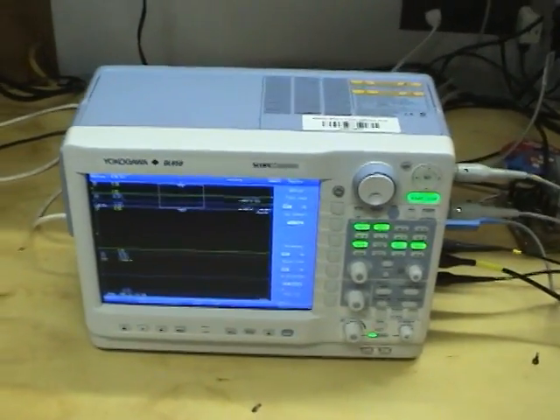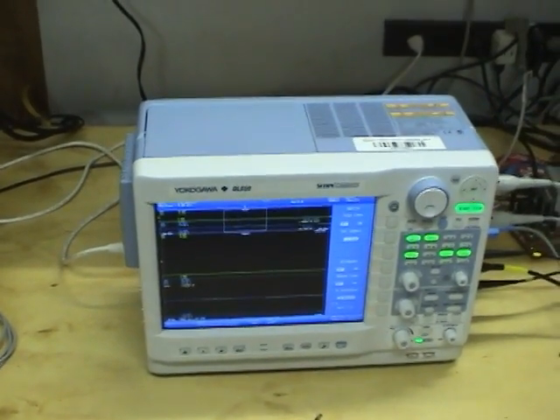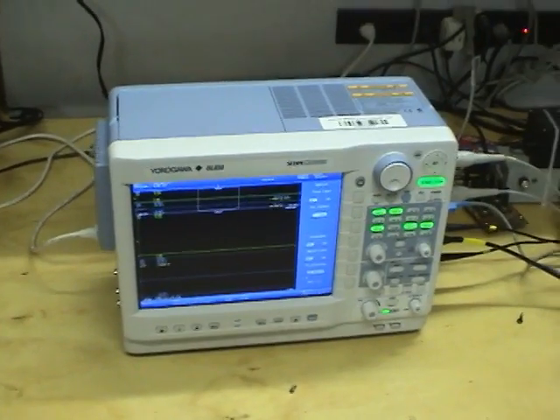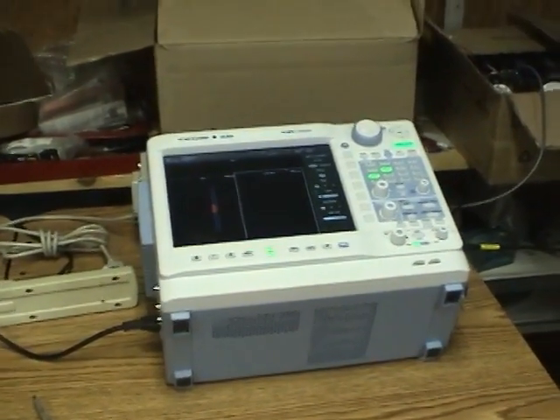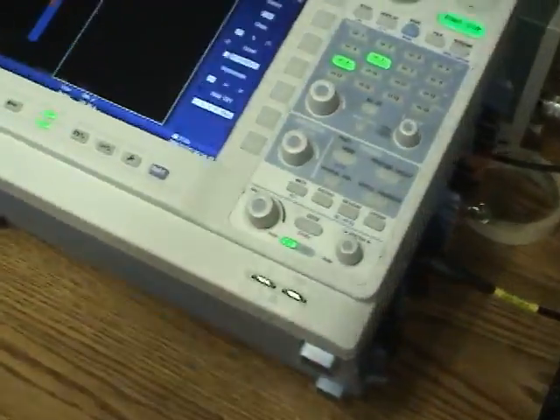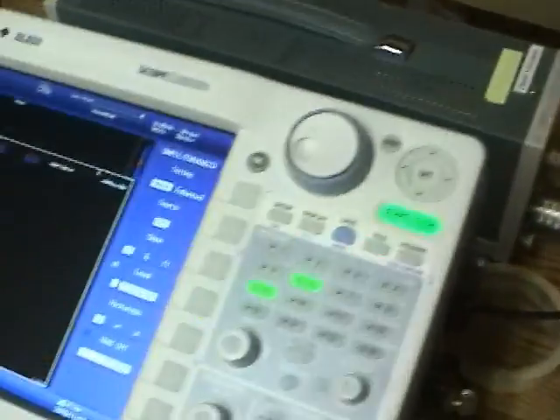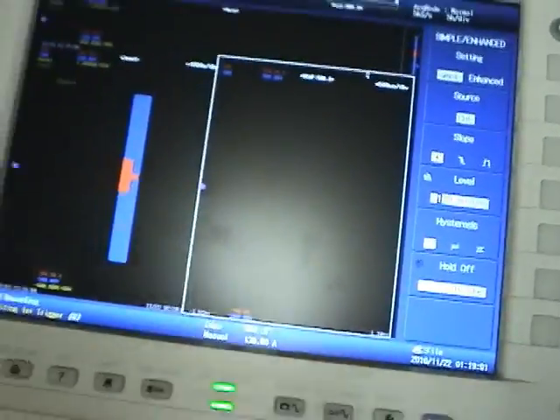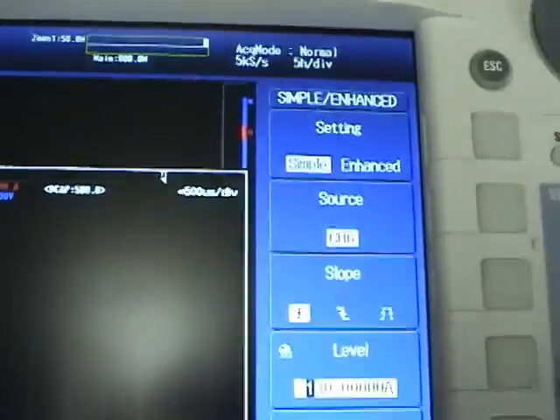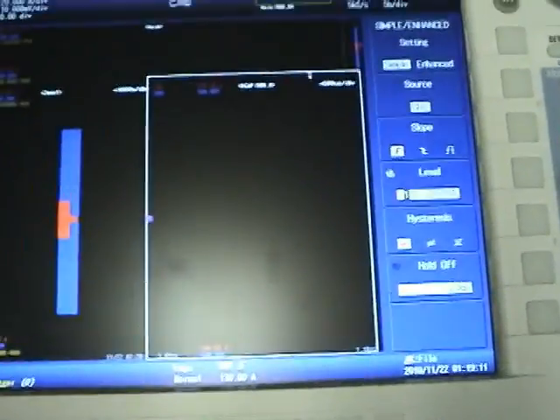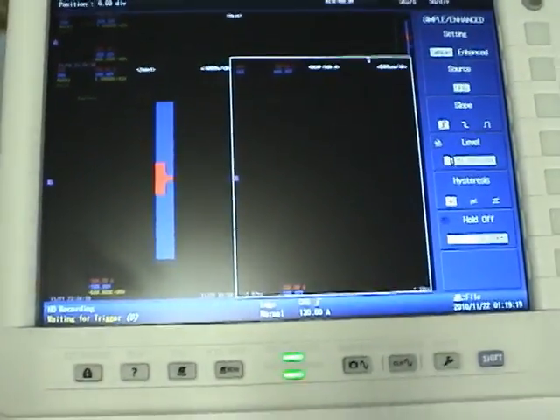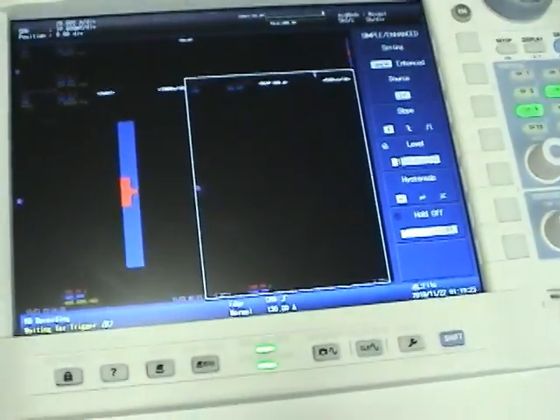Okay, let's try something different now. Let's try a long duration measurement. I'm going to hook this up to measure the power draw of the heat pump and we'll see how much energy it uses over a day. Okay, this is set up now. This little thing on the back for putting it in this position is actually quite handy so you can get to it perfectly when standing up. Anyway we've got the current probe measuring both current from the heat pump and the air handler, voltage probe connected up to a breaker here, and it's all set up and running. It's recording to the hard drive at 5 kilosamples per second, it was about 50 hours recording. And the dual capture is set to trigger on a current spike, a spike on the input current to try to capture whenever it turns on, whenever the compressor turns on at a higher sample rate, so we'll see how that goes.